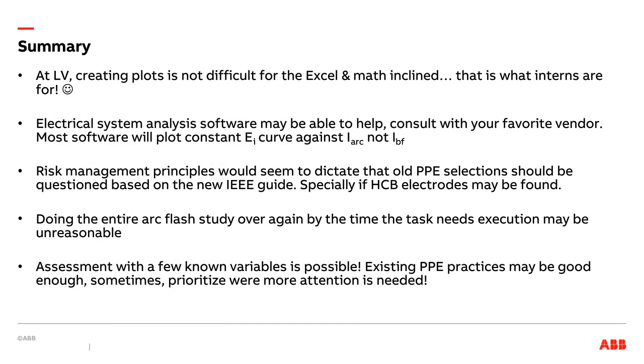Again, creating those plots, doing that analysis may seem difficult, but for somebody that has some inclination for Excel and a little bit of inclination for math, the IEEE standard gives you all the math. In fact, if you know somebody that was in the ballot that actually voted on the IEEE guide when it came out for public vote, and they have the old drafts, if they have draft number 1, all the formulas in that draft were in Excel format. You just have to cut and paste into Excel, make them into variables, and voila, it works almost automatically. You don't have to figure out how to translate from math language to Excel language, because it was originally put in Excel language.